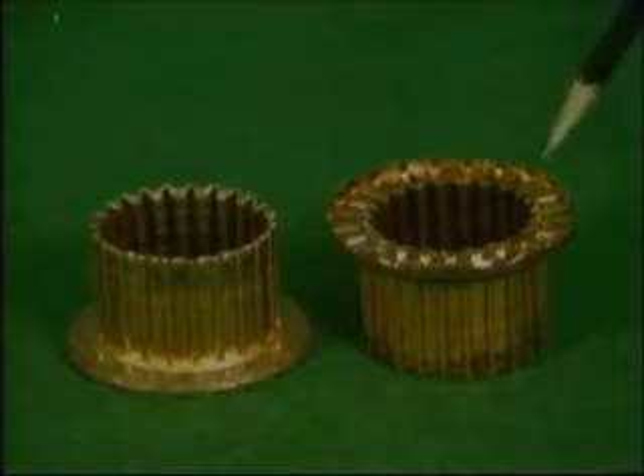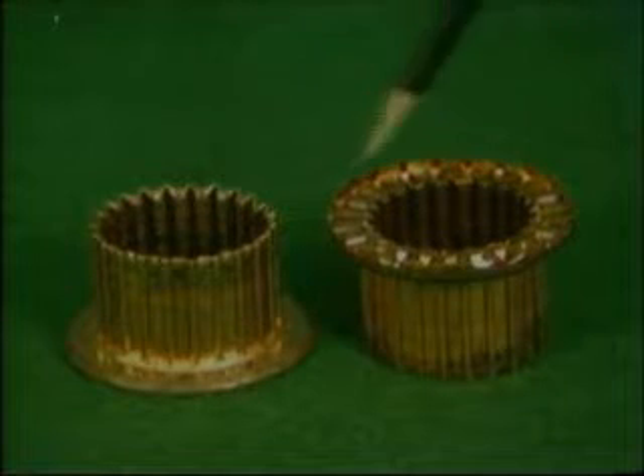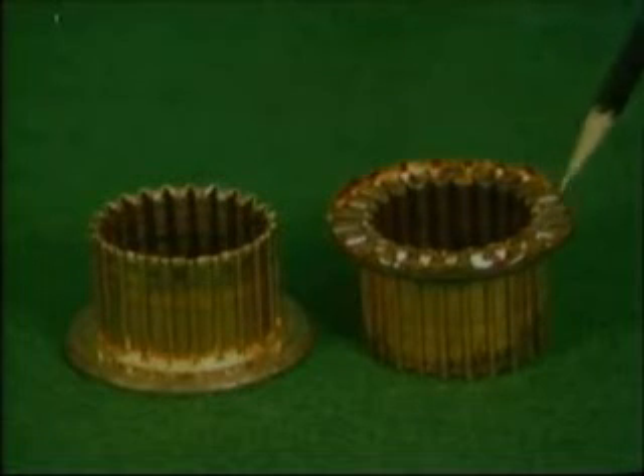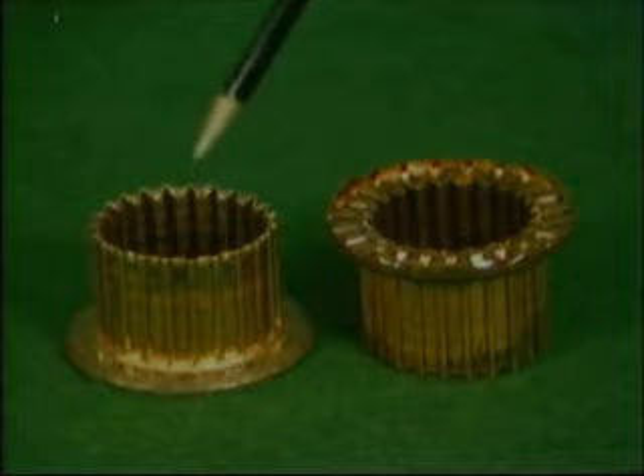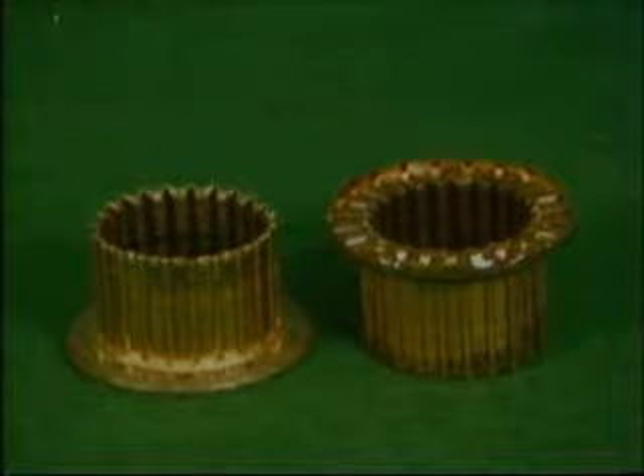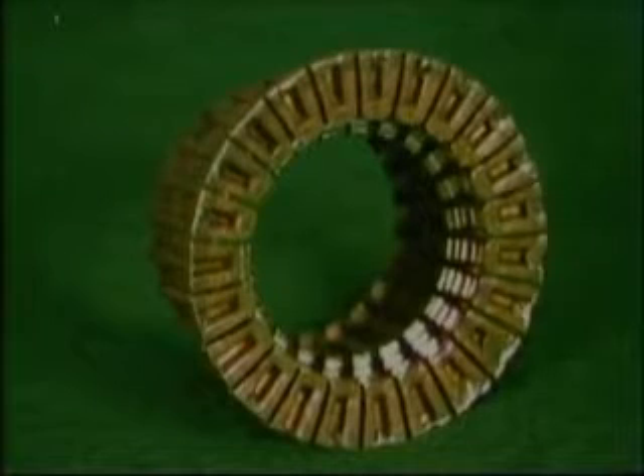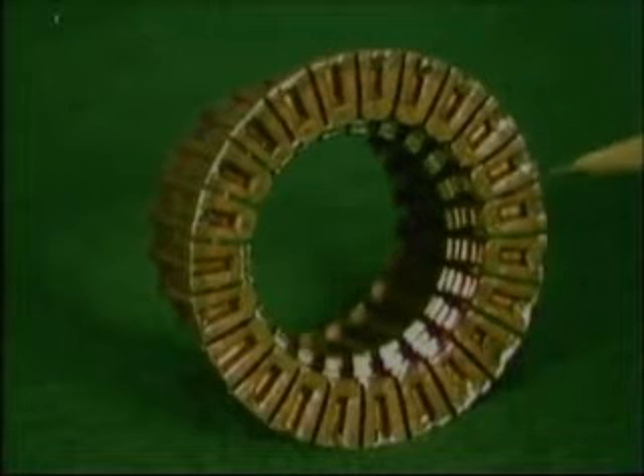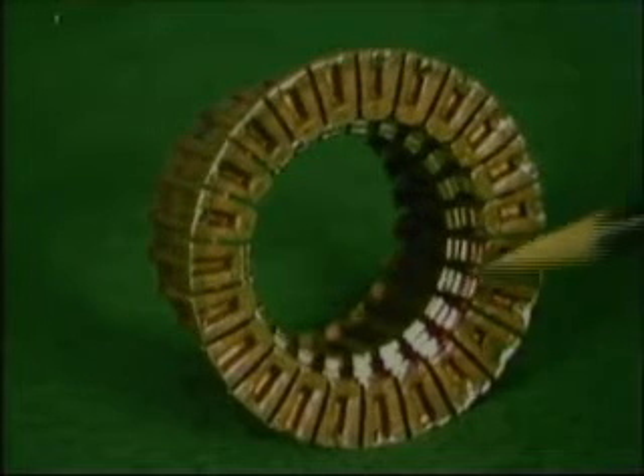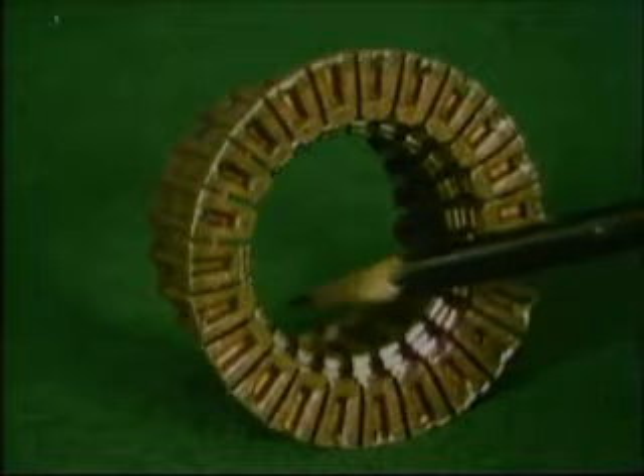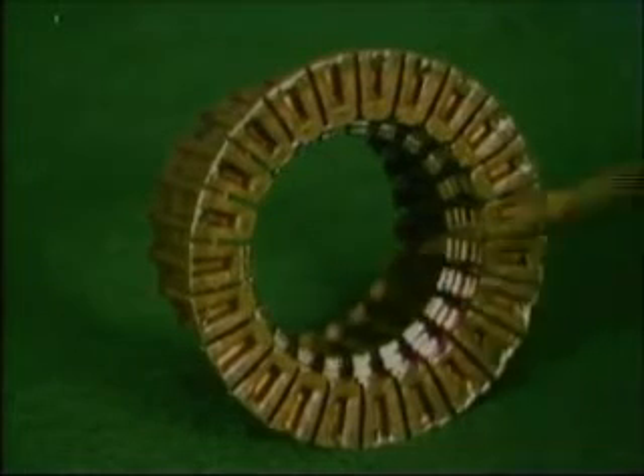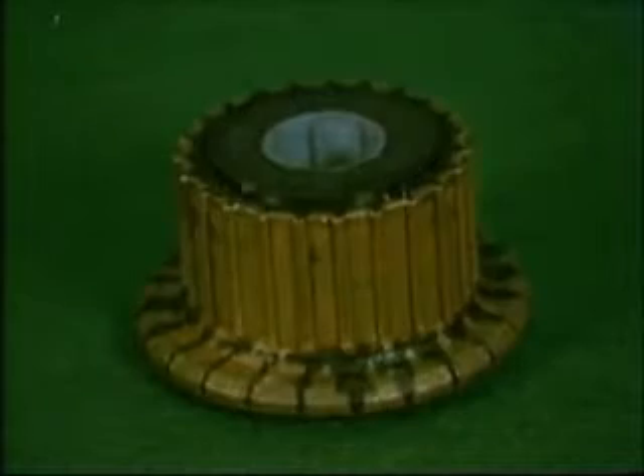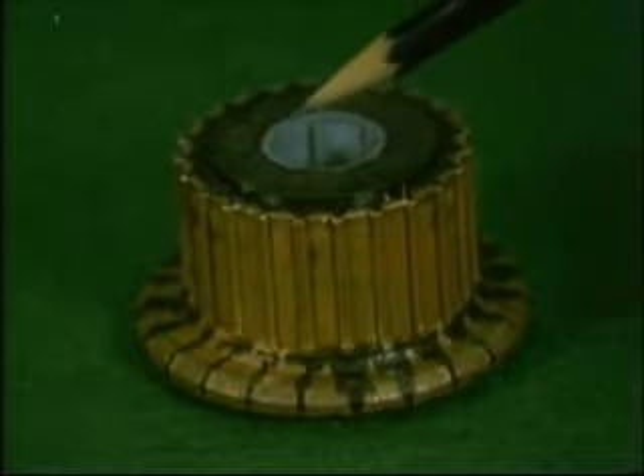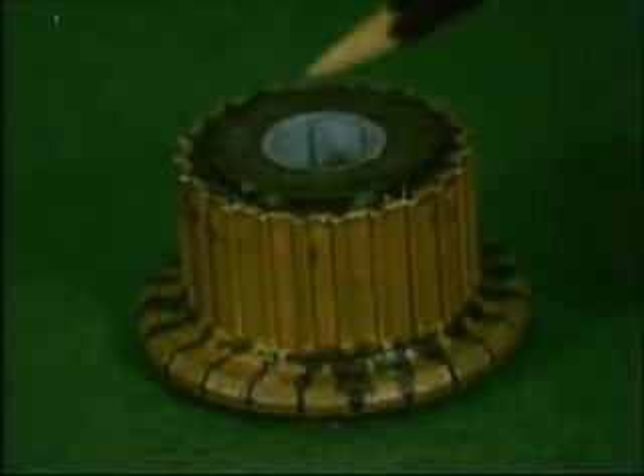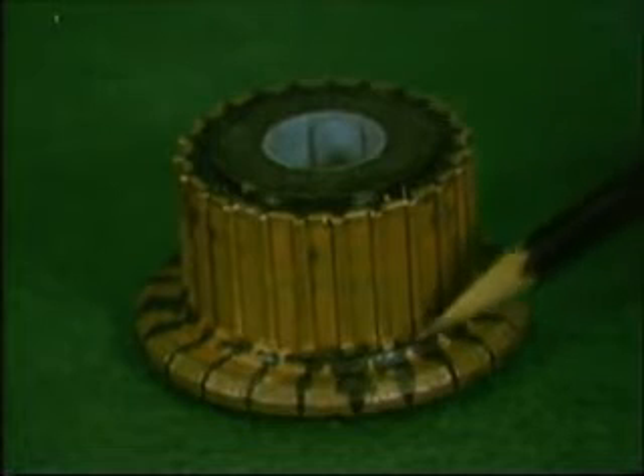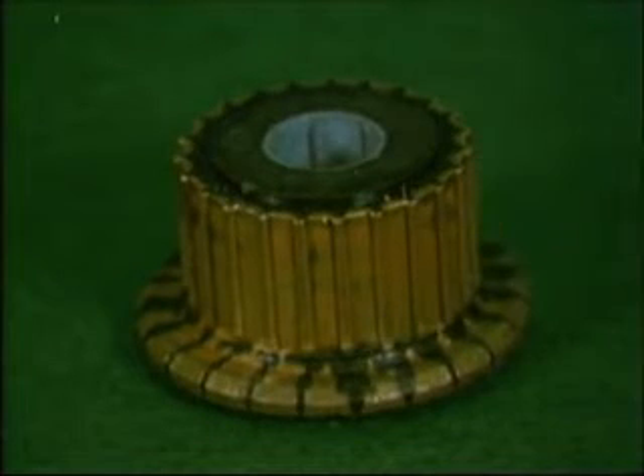The formed blank must be faced and trimmed free from flash. Thin elevated wall sections are formed to facilitate separation in final assembly. The riser bar ring is pierced to receive insulation in a phenolic molding process. Tangs are cold curled inside on both ends to anchor firmly to the molding material. The ring is phenolic molded to a die-cast core on automatic pallet-type presses designed by Delcotron and are unique in the industry.